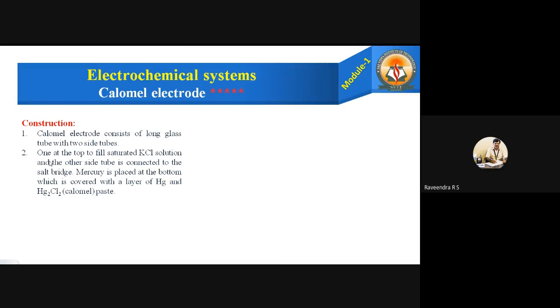The side tubes serve specific purposes: one side tube at the top is connected to the saturated KCl solution, and the other side tube is connected to the salt bridge. So one side tube is used to fill the saturated solution of potassium chloride, and the other side tube is used to connect the electrode to the salt bridge during determination.